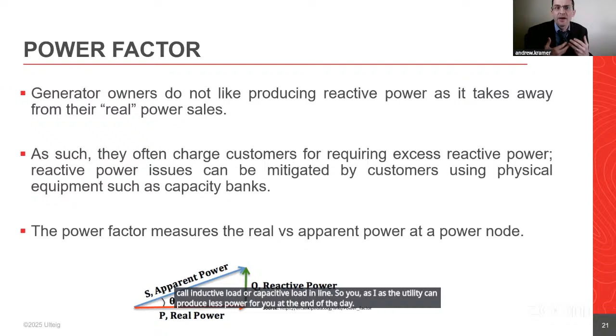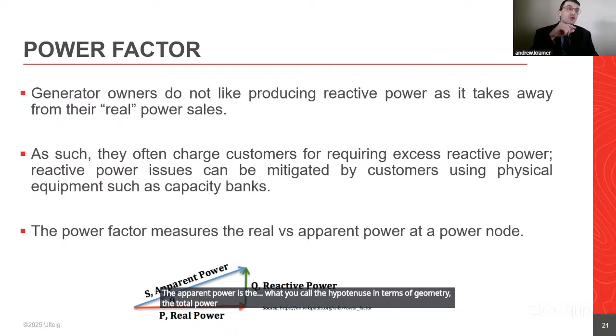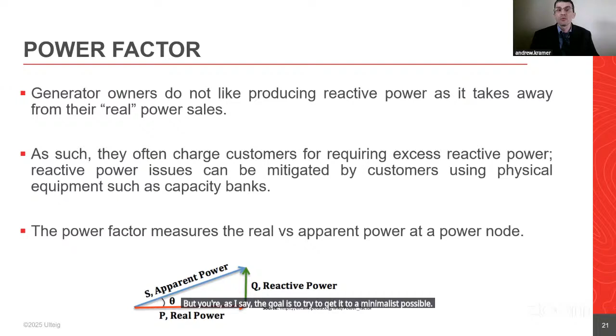We can't complete a discussion on reactive power without showing the power triangle and power factor. Power factor measures real power versus apparent power, the hypotenuse in geometric terms, representing total power produced. Real power divided by apparent power gives you the power factor. The goal is to get that as close as possible to 1, where real power equals apparent power, since you then produce less reactive power. You'll always need some, but the goal is to minimize it, which is why we encourage customers to do that.